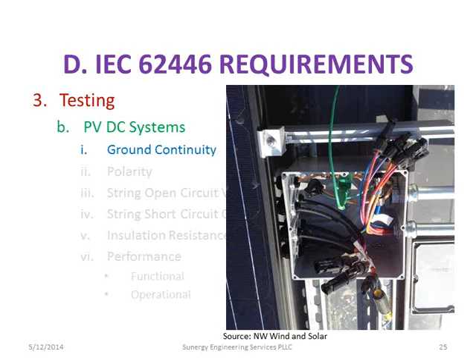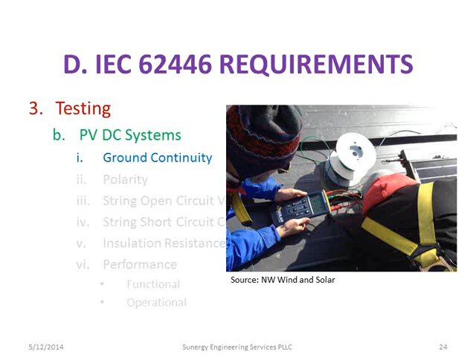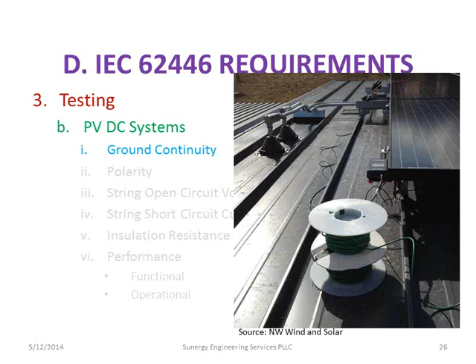So this is a little different. On a lot of our meters, we can do a continuity test where we just get the little beep. You go beep, and everybody thinks that's good. I have a connection, but that doesn't tell you the quality of the connection. You actually have to send some current through to get a good resistance measurement to know exactly what your resistance is. So this is actually a pretty critical step. You can see we have a long spool of wire, so we can walk down the array and check different modules if you need to. Most of the time, for commissioning, you might just check the module on the end.